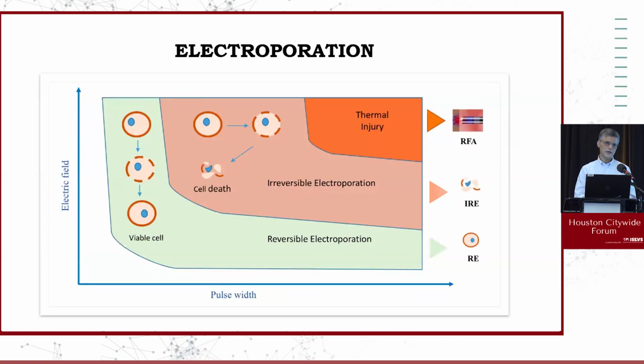So pulse field ablation is based on the concept of electroporation. Electroporation is when a very high electrical field is applied to living cells. The cell membranes develop tiny nanopores. Depending upon the strength of the electrical field, this can cause a reversible electroporation in which the cells will leak contents but won't die. Or if the electrical field strength is fairly high, it will cause irreversible electroporation, which will lead to eventual cell death. And if the electrical field is increased in intensity and pulse width more, it will eventually cause more thermal damage also. So that's the concept behind pulse field ablation.